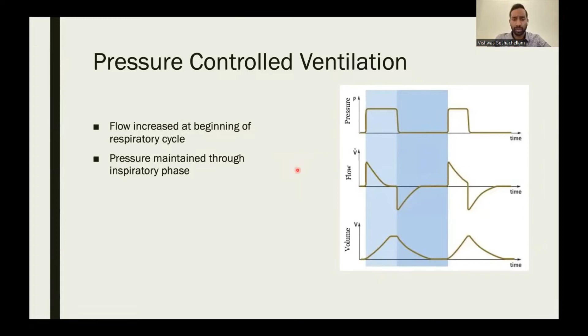But there's another mode of ventilation that should be available on your machines that I'm talking about next, which is actually the best of both worlds if you can use it. Pressure regulated volume controlled ventilation combines the first two. This may be a little complicated, but it's basically a combination of volume controlled ventilation and pressure controlled ventilation. So it's a combination of the decelerating flow pattern of pressure controlled ventilation along with the guaranteed volume delivered.